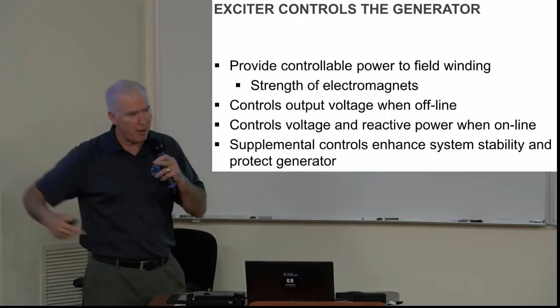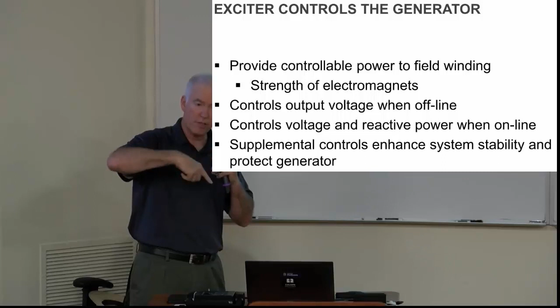The governor controls the turbine, controls the wicket gates and the power that's generated. The exciter controls the generator. It feeds, it takes a little bit that's produced by the power, turns it back into DC, and sends it into the rotor that generates the electromagnetic north-south poles.